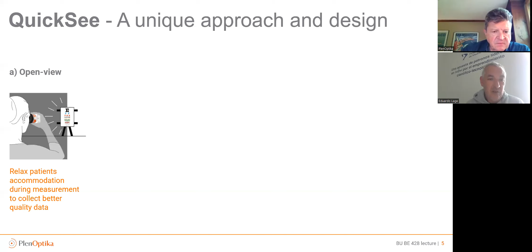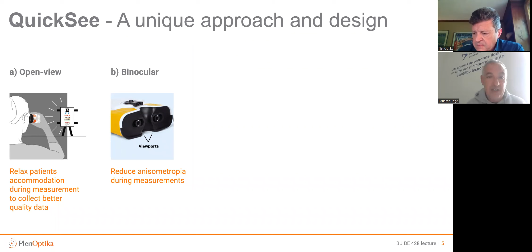Apart from that, and in order to mimic a natural viewing experience, the device is binocular and can measure the patient while the patient is looking through the device at a distant target. Okay, it's a natural viewing experience. And because this device is binocular, we have tested that it can reduce anisometropia during measurements.